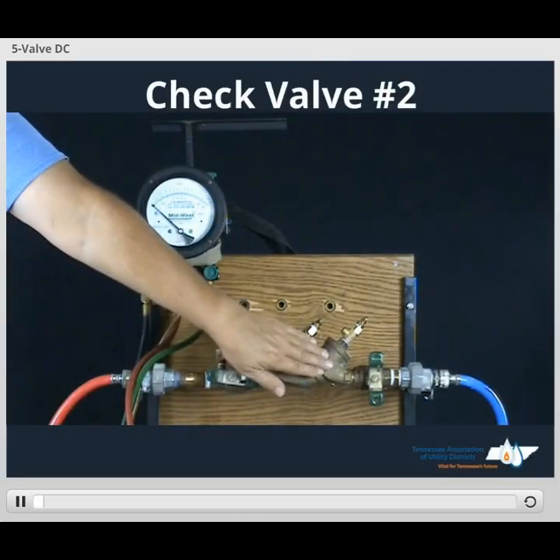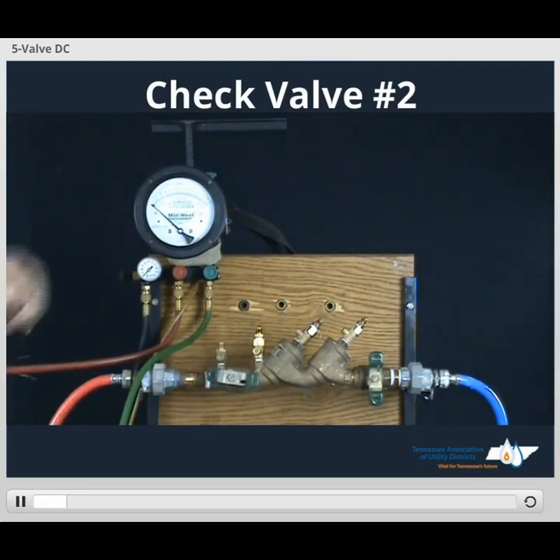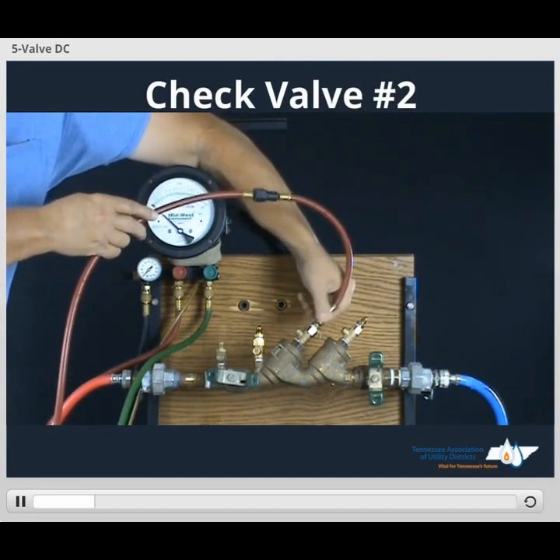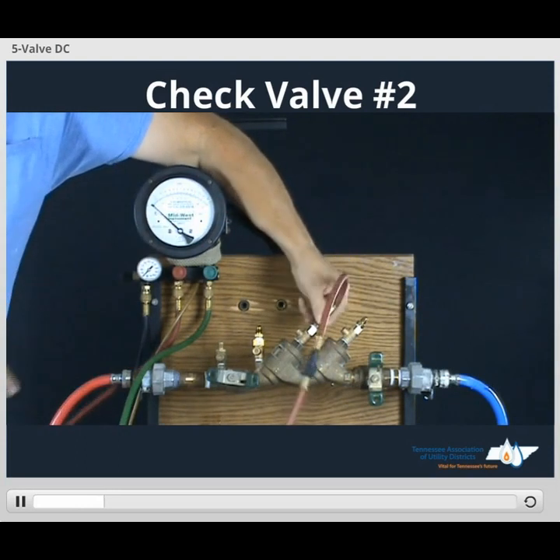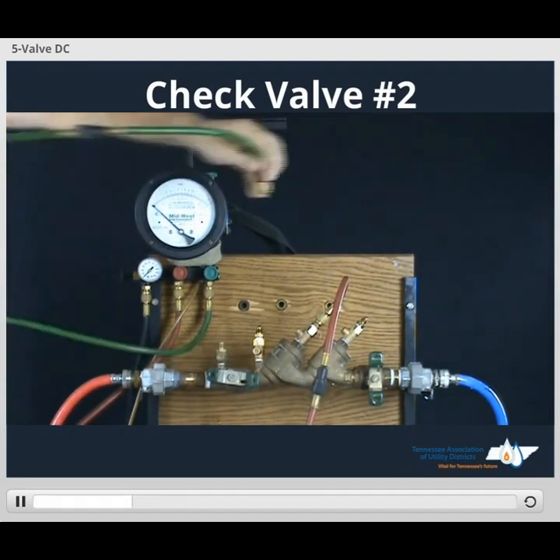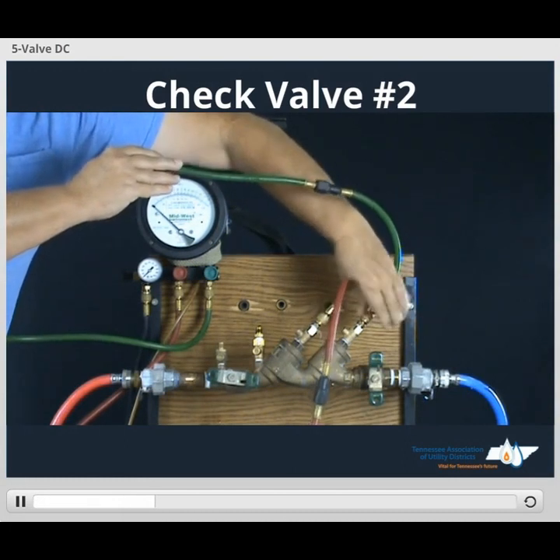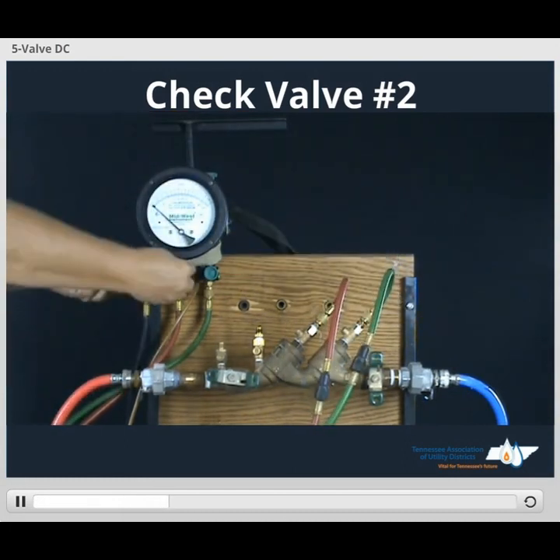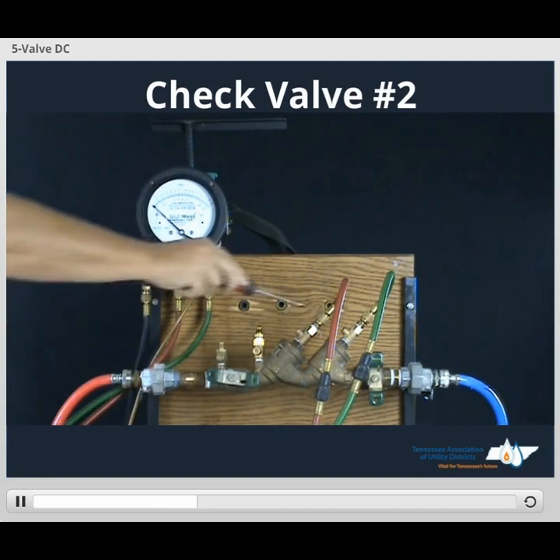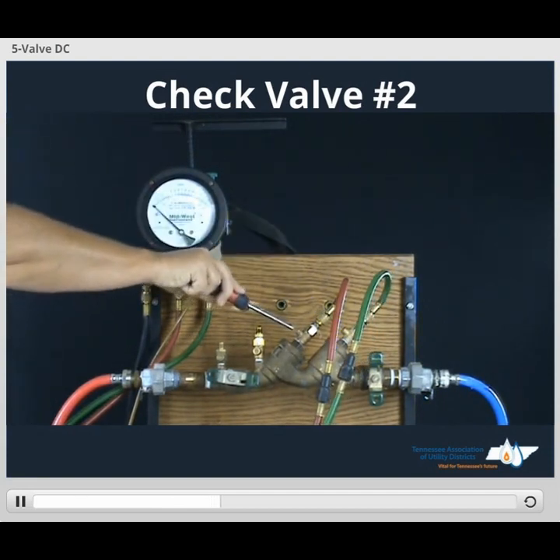In order to do our last test — testing check valve number 2 in direction of flow — we'll take our high side hose, connect it to test cock number 3. Take our low side hose, connect it to test cock number 4. Make sure all of our valves on our gauge are in the closed position. Take our screwdriver, open test cock number 4, open test cock number 3.